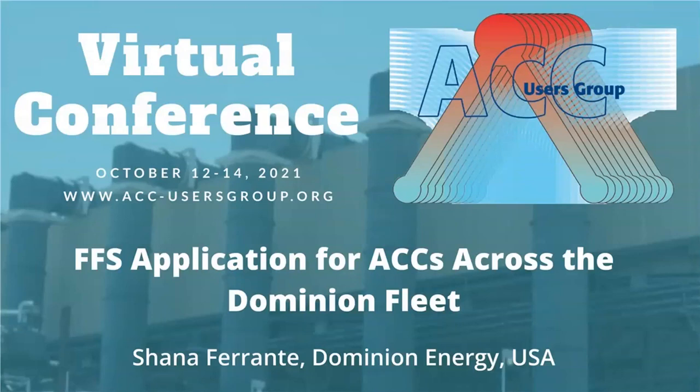Good morning, Barry. Good morning, everyone. Interesting presentation. You made the comment that the ACCs were fully protected, but in the photos and in the video, you could clearly see flash rusting in there, the orange. Have you got any comment on that?